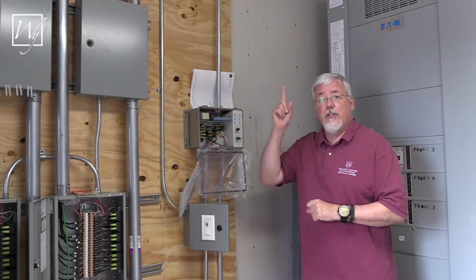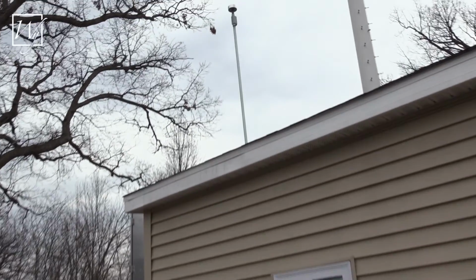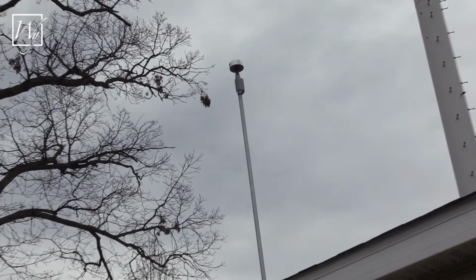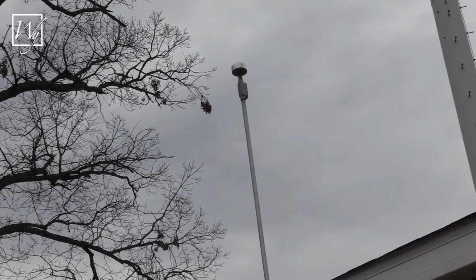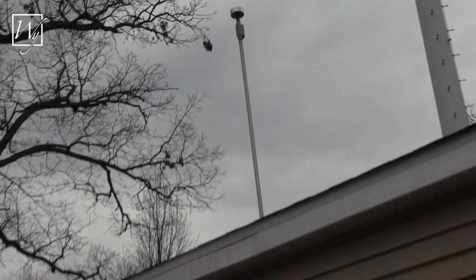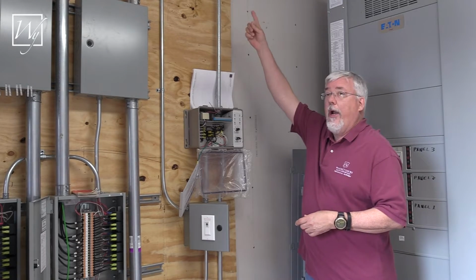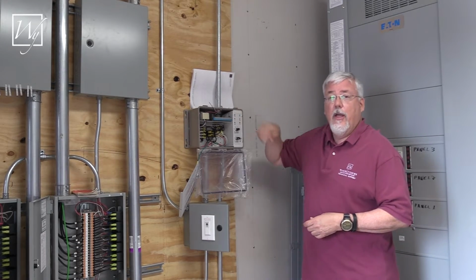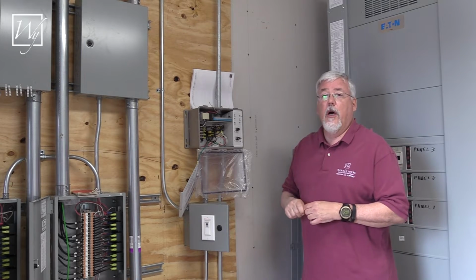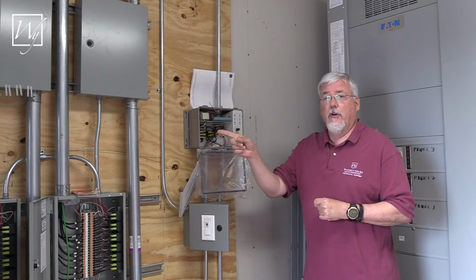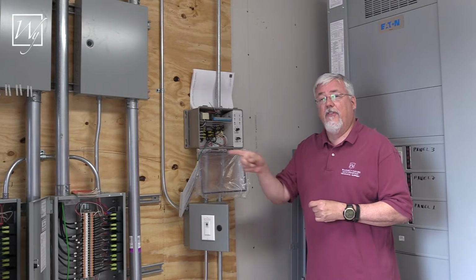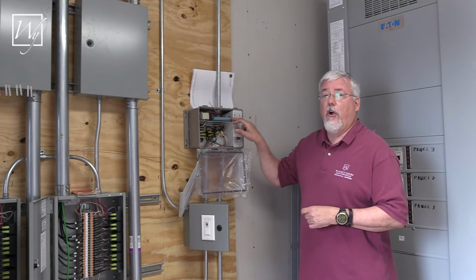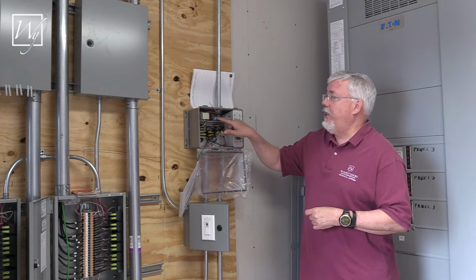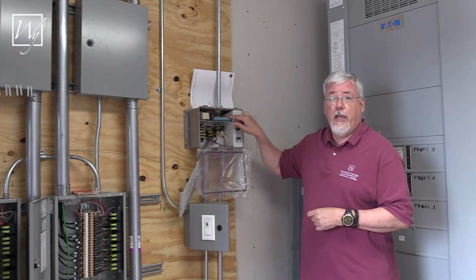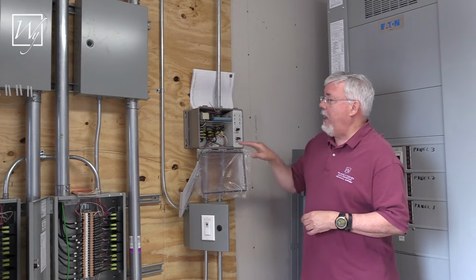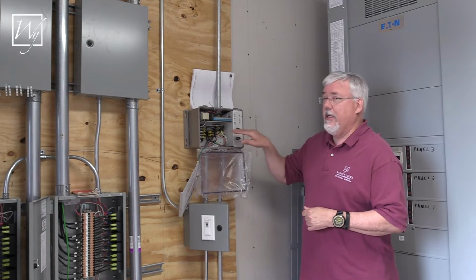We also have an aerial sensor upstairs above here, which is made to see what the temperature is, and also if it's raining or snowing or not. And so that wire is coming through this conduit down here. And then we will also have another wire coming from the pavement sensor, which is installed out in the pavement, and it will be connecting in here also. So all of your connections here at the top will be your low voltage connections, and all of your high power or line voltage connections will be done in here.